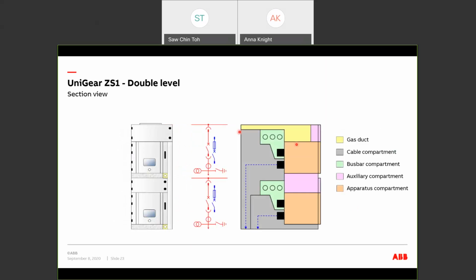This is the typical sectional view of the double level panels. So we have the arc duct running at the top of the switchboards. The main low voltage compartment is actually situated in the middle. This compartment will house 2 sets of protection relays for the 2 breakers or contactors installed in the panels. There's another smaller low voltage compartment at the top of the cubicles. This is for the interpanel wiring or the customer external connections.